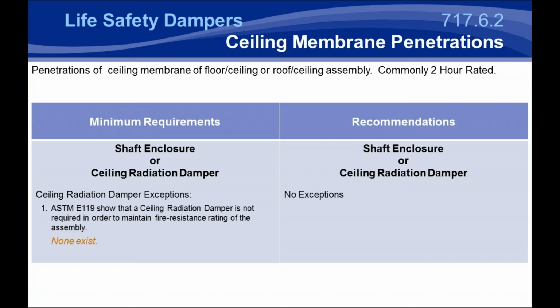So when I was talking about the corridors earlier, any corridor that has a rated ceiling and a generic duct or damper called out, say a 12 by 12 duct, and typically originally they were asbestos lined, but as we got away from using those types of materials, there'll be a flapper type damper or hinge door type damper called out for protecting that opening, and then you can use any UL 555C rated damper.